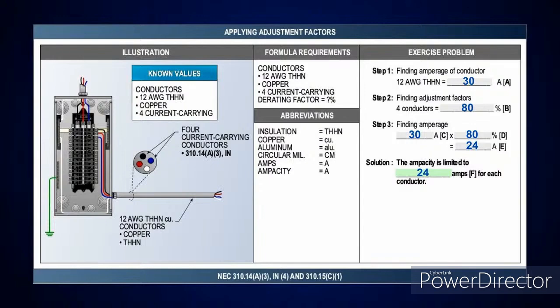All right, so now if you go over and you look at Table 310.16 for this illustration, we've got 4 current carrying conductors, and we're using number 12 AWG, American wire gauge, of course, that's what it means, THHN. Now, I want to point this out one more time for anybody that's going back, following all this, trying to get everything in their mind again. Remember, go look at Table 310.4, and in this case, you're looking at the first table. And when you go over and pick that up, it's going to tell you the THHN is good for what? 90 degrees C. Now, if this was THWN, you could only use the 75 degrees C column. Okay? That's what you've got to look at, the type of conductor that is in there, in order to know which one of the columns you can use.